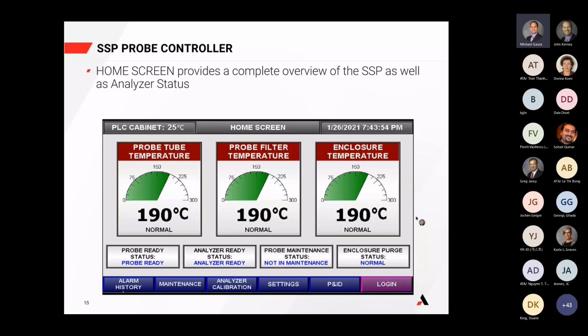So the SSP probe controller's home screen is what we're looking at right here. In it, you can see what the temperatures are, not only at the probe tube, which Rod was pointing out is so important to maintain above the dew point, because we do see a lot of damage occurring to probe tubes and other components. So what we do is we keep that temperature, in this case, at 190 C. And from the home screen, the user will be able to see where that temperature is at. They'll also be able to see if there's any issues further downstream.